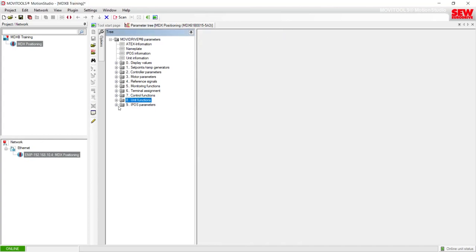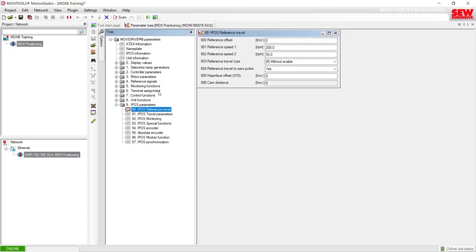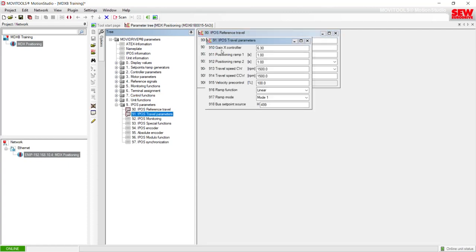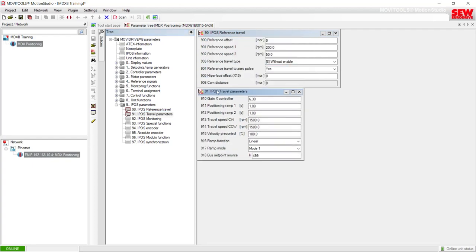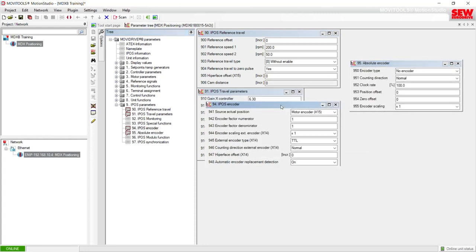Lastly, folder group 9 is dedicated to IPOS program functions. If you're using an application from SEW, a lot of this will be set automatically through the application module. In some instances, if you're using a custom IPOS program, you would also need to come into this parameter group and make additional changes to the IPOS program settings. Common ones include the reference travel settings, travel parameter settings, IPOS encoder settings, and absolute encoder settings.